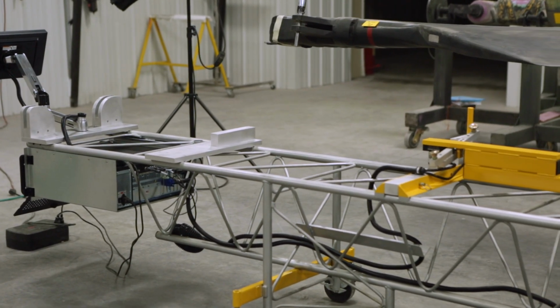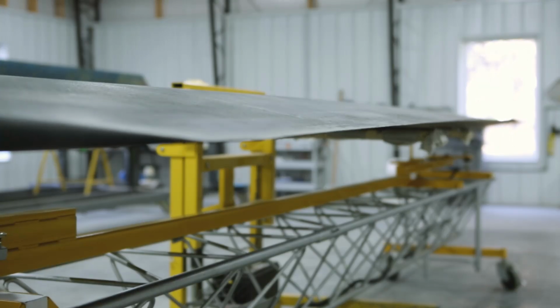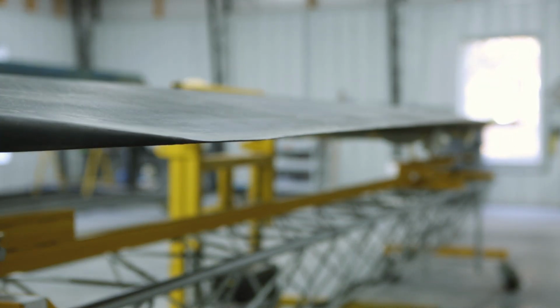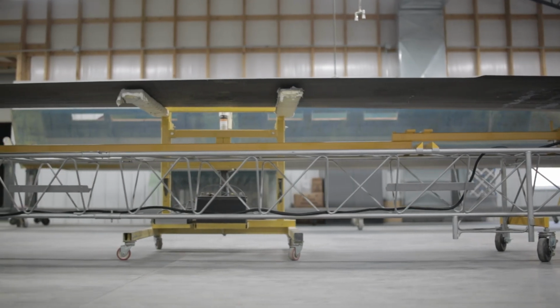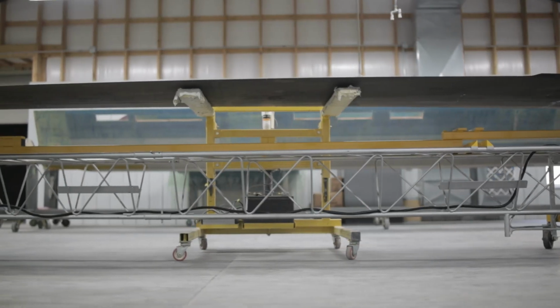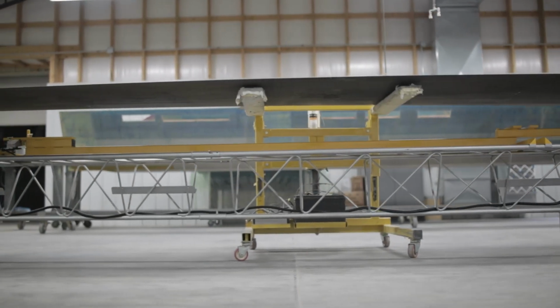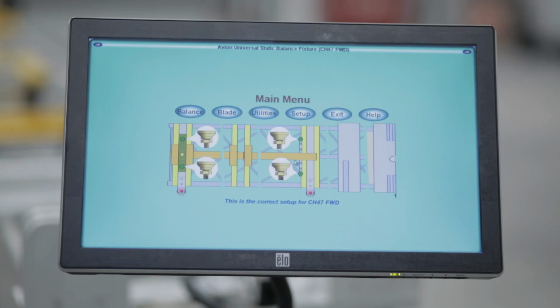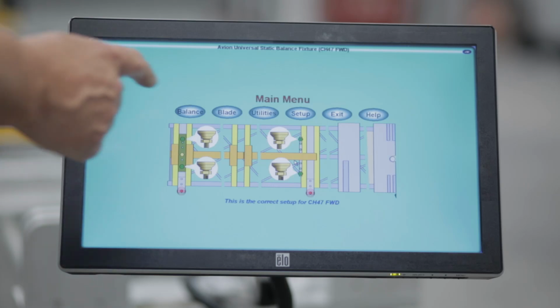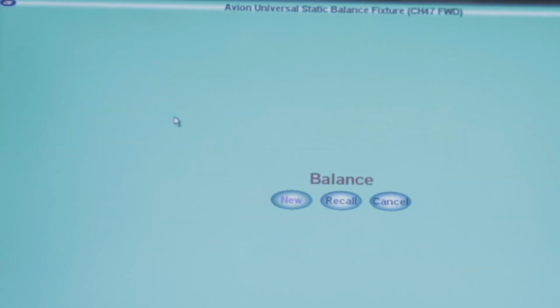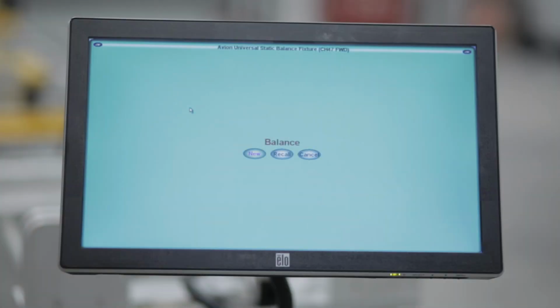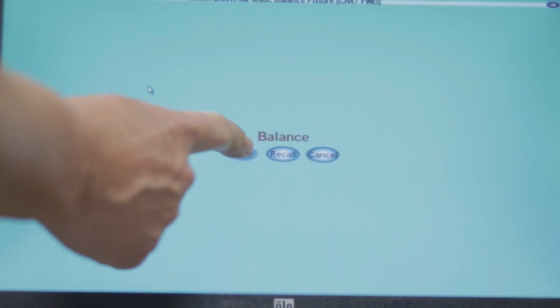If it is set up correctly and the correct blade type software is indicated, go ahead and run the program. The blade is probably way out of tolerance because of water, excessive paint, or poor repairs. We have set up the machine to balance a Chinook forward rotor blade. The blade is not loaded, but is ready to be loaded and the right software is selected. Select Balance. This is a new balance for the day, so we will select New and enter the operator's name.